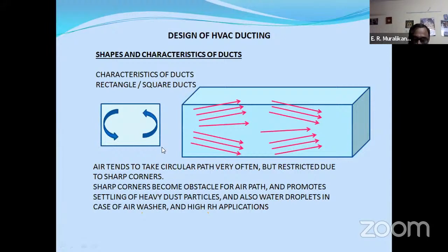When you study centrifugal force and air movement in these ducts, the rectangular duct has this drawback. When you go for an air washer, the water droplets will go and settle in these corners, and it will promote settling of dust particles and other things. So when you go for an air washer system, preferably go for a round duct. This is my suggestion.